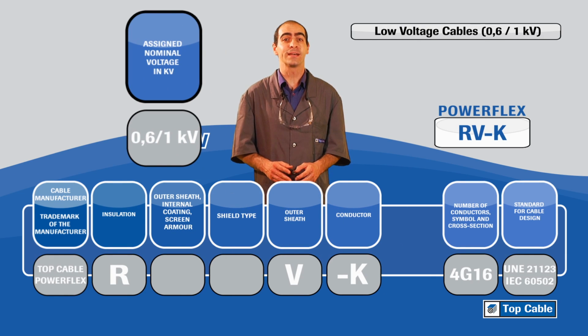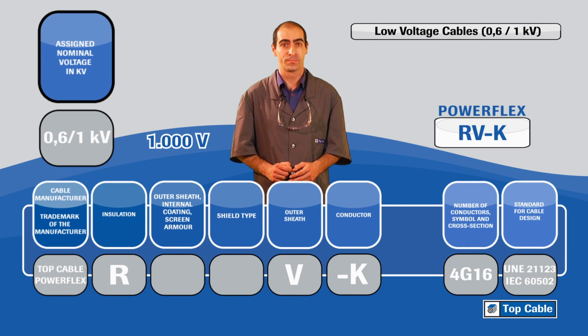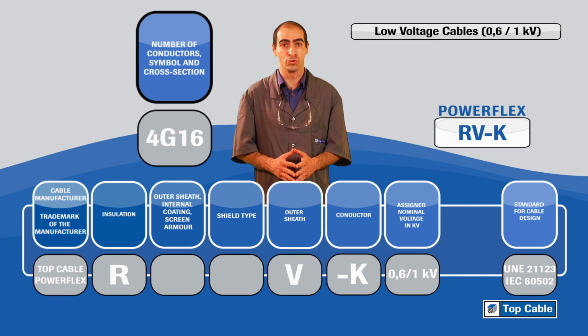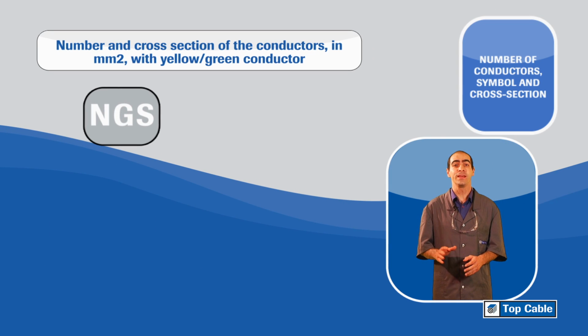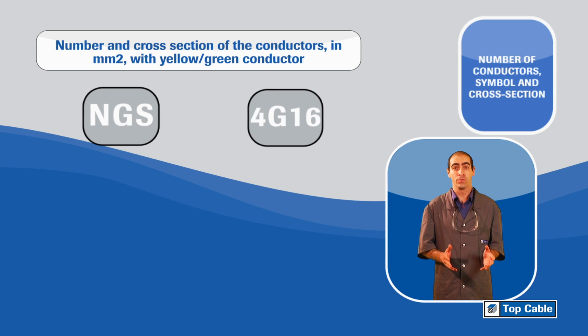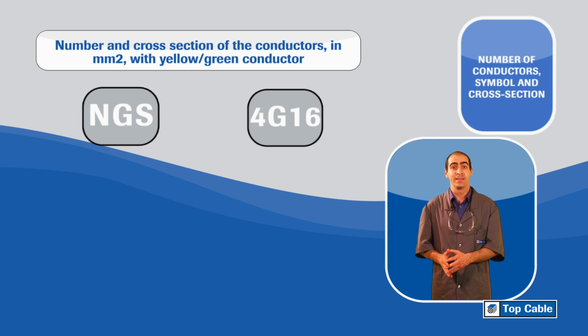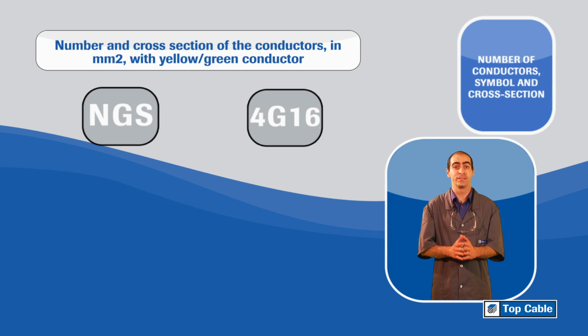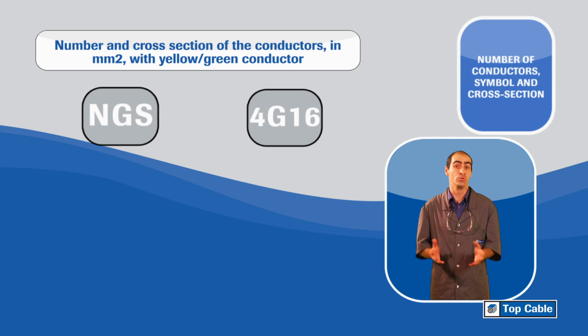0.6 to 1 kilovolts equals 1000 volts. Lastly, the number of conductors and their cross-sections are defined. NGS, number and cross-section of the conductors in millimeters squared, with yellow-green conductor. For example, 4G16 means 4 conductors of 16 millimeters squared, one of them being yellow/green.